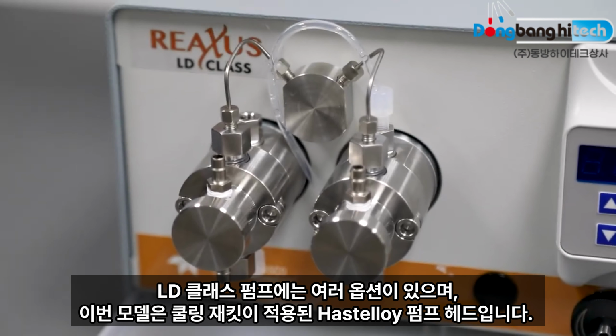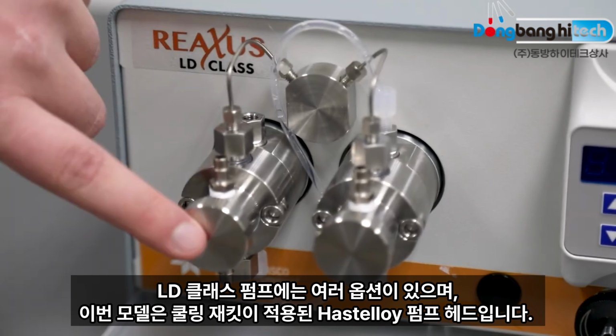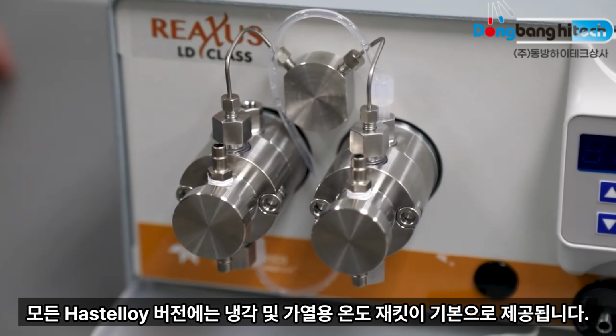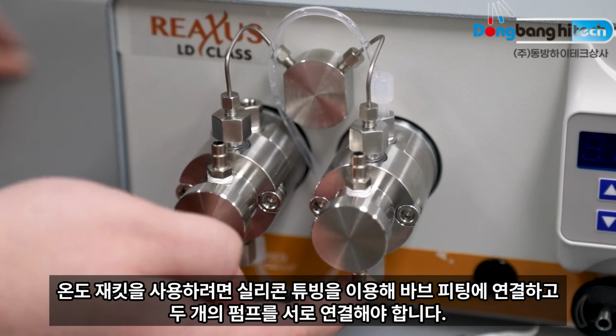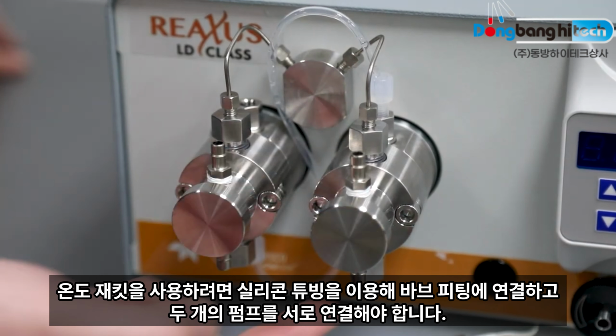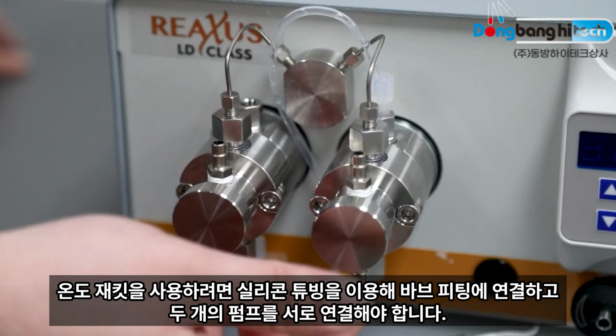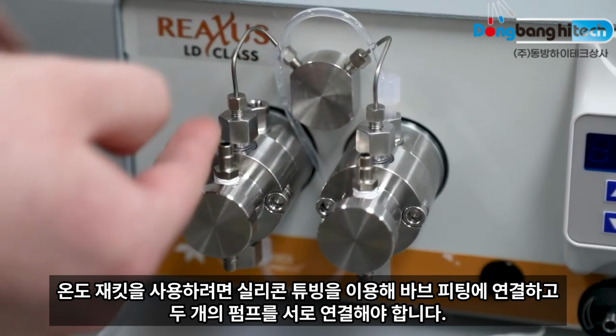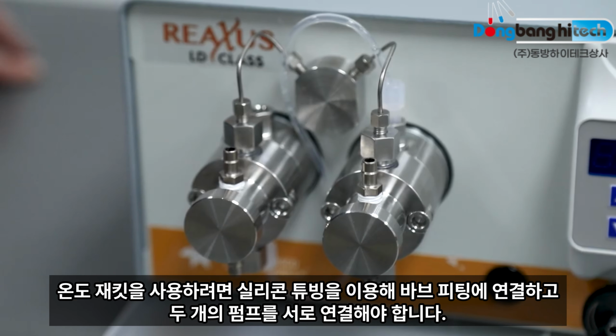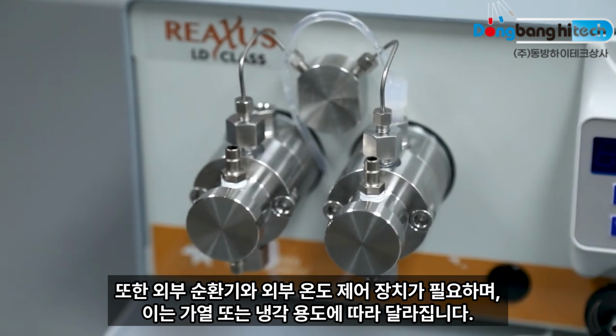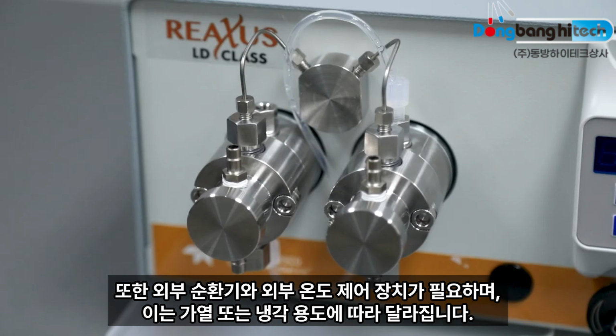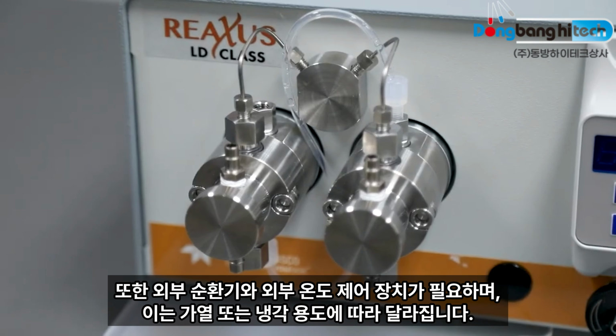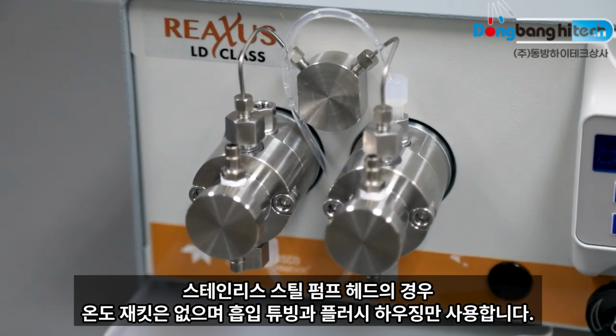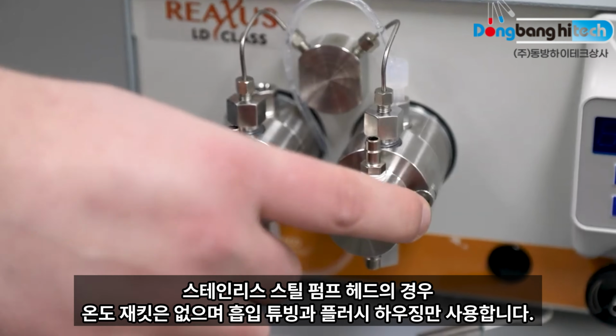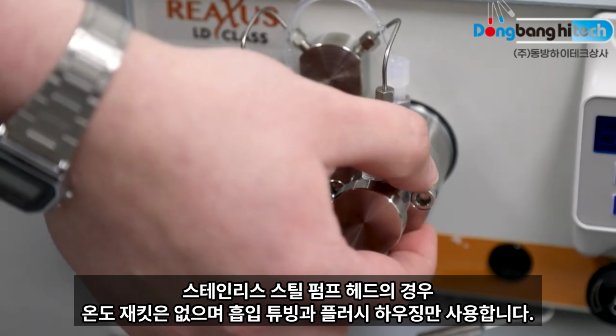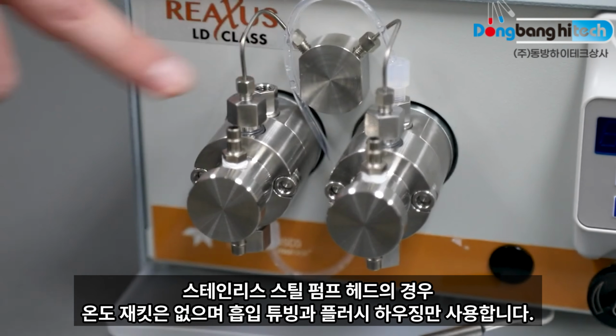This specific pump is going to be the Hastelloy pump head version with the cooling jackets. All Hastelloy versions will come with these cooling heating temperature jackets. To operate these, you will need silicone tubings to your barb fittings on your inlet that can connect between the two pumps. You have an outlet. You will need some sort of recirculator and external temperature control for those specific applications, whether you are heating or cooling. On a stainless steel pump head, these temperature jackets will be missing, and you will just have your inlet tubing lines and your flush housings.